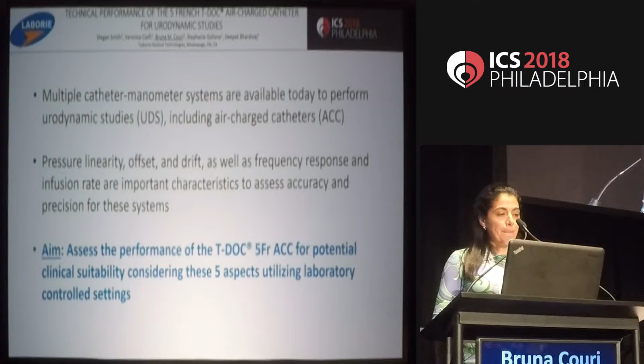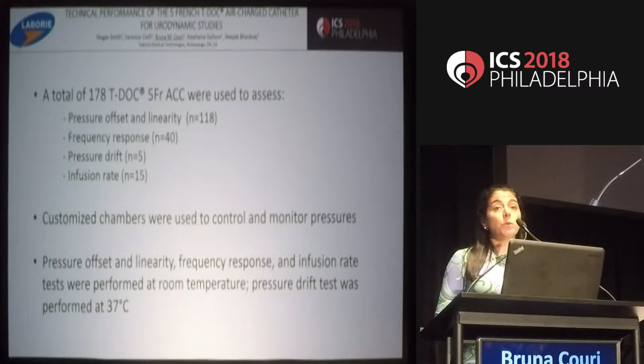A total of 178 TDOC 5-French air charge catheters were used to assess pressure offset and linearity, frequency response, pressure drift, and infusion rate. Customized chambers were used to control and monitor pressures. Pressure offset and linearity, frequency response, and infusion rate tests were performed at room temperature. Pressure drift test was performed at 37 degrees Celsius.